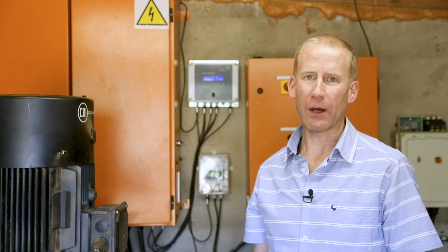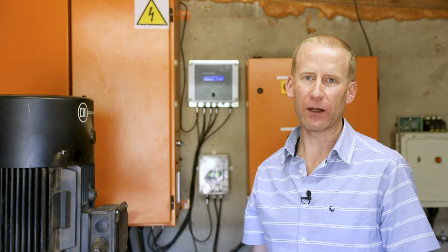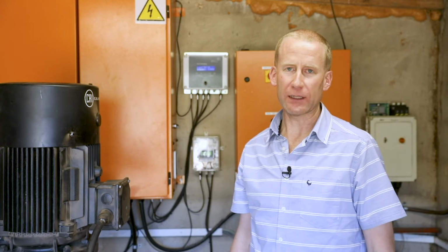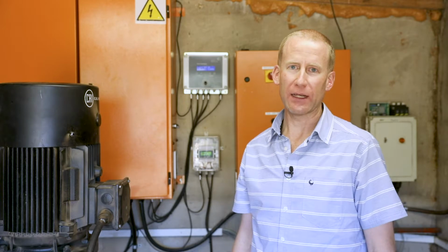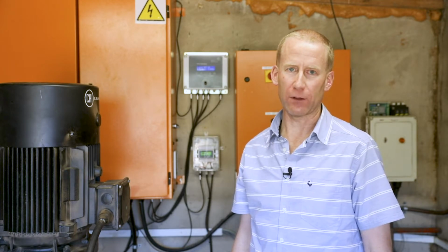However, both pumps can be run at once, meaning that the transformer can now deliver 360 cubes per hour. This gives a daily flow rate of 8,640 cubes. This is an 80% increase in volume that can be pumped by that transformer in a single day without having to make any changes to the actual pumps themselves.